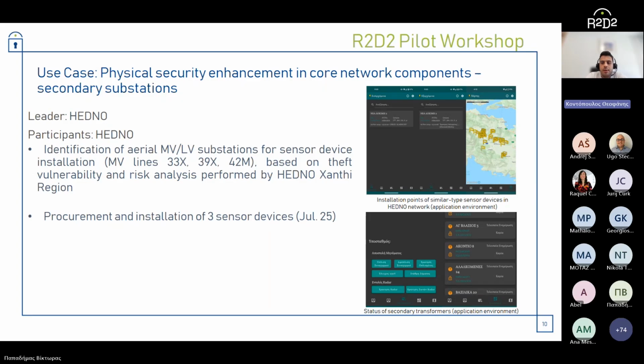This process, successfully carried out by the local head in Xanthi region department, focused on identification of 3 points, one per line, where frequent phenomena of aerial substation thefts take place in the Xanthi network. At those 3 points, the target was to install sensor devices, which my colleague Victor mentioned previously.